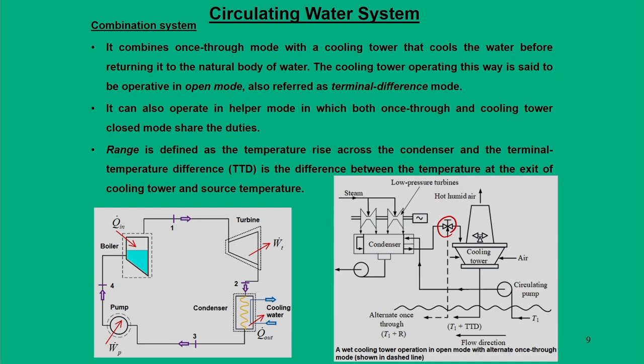In both cases, the initial water temperature is T1. In once-through mode the final temperature is T1+R, while in combination mode the final temperature is T1+TTd. TTd is the terminal temperature difference - the difference between the exit temperature of the cooling tower and the source temperature. Range is defined as the temperature rise across the condenser.